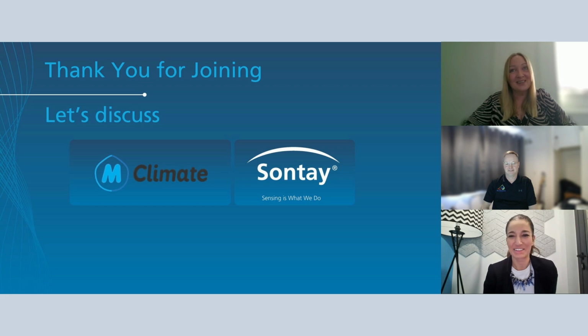But it's how you want it. Typically in the commercial BMS world, people don't tend to use the cloud. They tend to want their data to go into the BMS controller, which is why you will see a gateway taking that information straight through to BACnet objects and into the BMS controller.